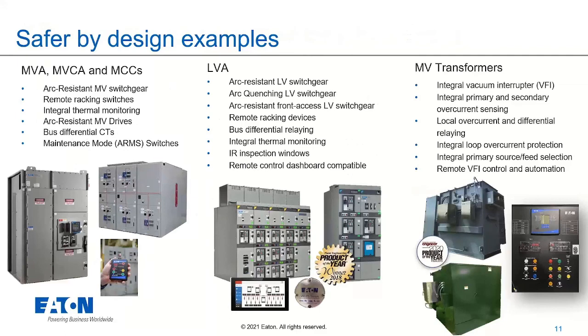Just a few examples here - these are some Eaton products, but you'll find very similar stuff throughout the industry in the medium voltage control assembly world or motor control center world. You'll have your arc resistant MV switchgear, remote racking, and thermal monitoring. In the low voltage assembly world, in addition to arc resistant, we're now seeing arc quenching, where you essentially create bolted faults to quench and remove the fault from the scenario. They do similar things to MV - remote racking, thermal monitoring - but you also see remote dashboards for interfacing with your products.